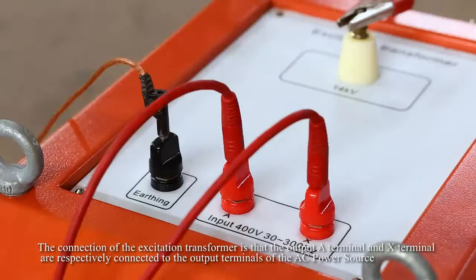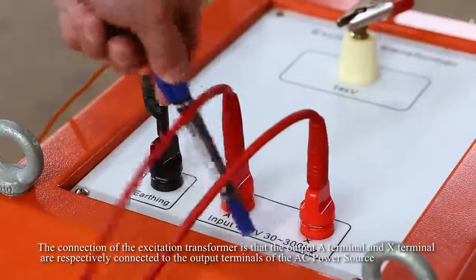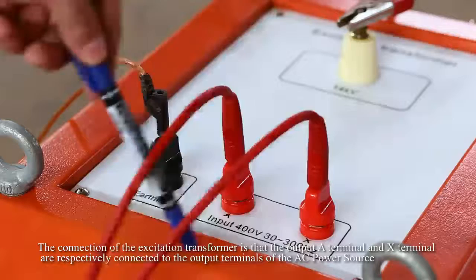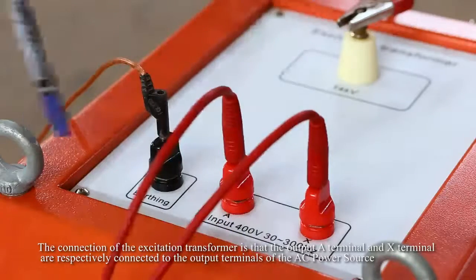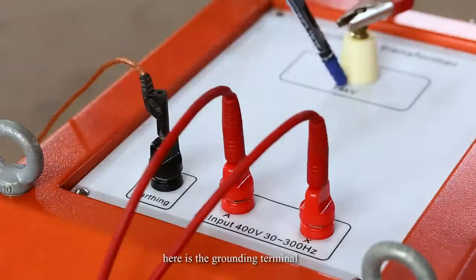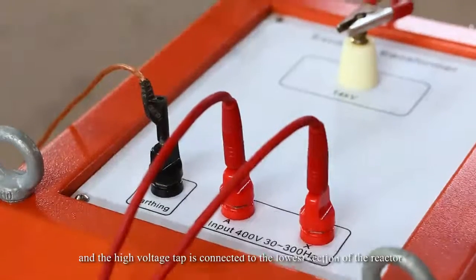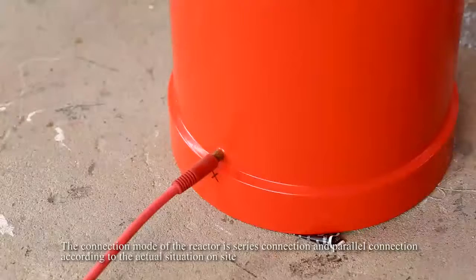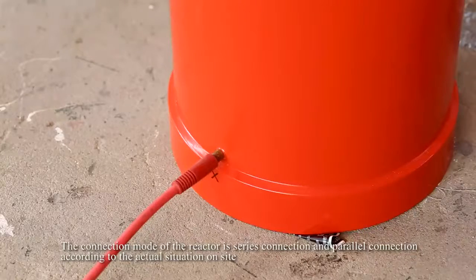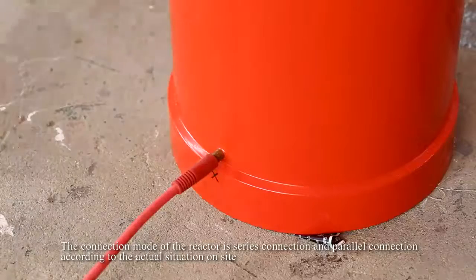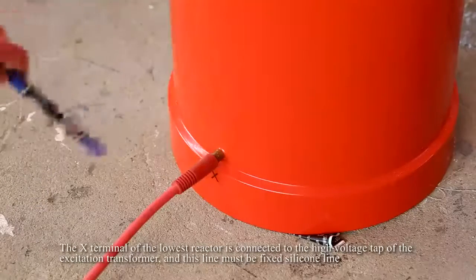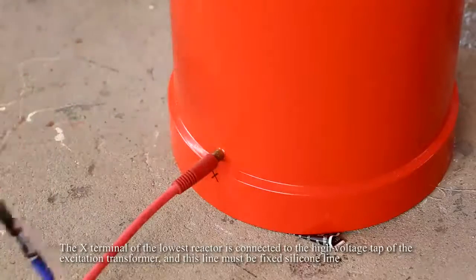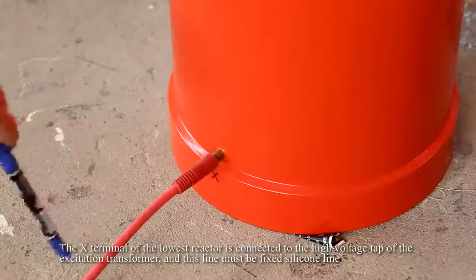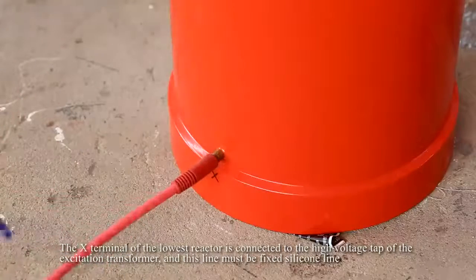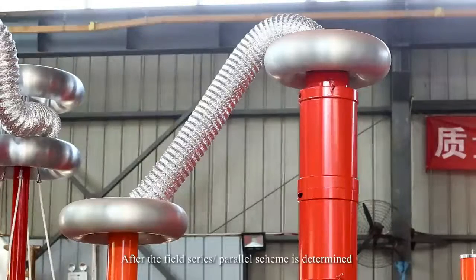The connection of the excitation transformer is that the output A terminal and the X terminal are respectively connected to the output terminals of the AC power source. Here is the grounding terminal, and the high voltage tap is connected to the lowest section of the reactor. The connection modes of the reactor are series connection and parallel connection, according to the actual situation outside. The X terminal of the lowest reactor is connected to the high voltage tap of the excitation transformer, and this line must be a fixed silicone line. Whether to use series or parallel is determined in the field.